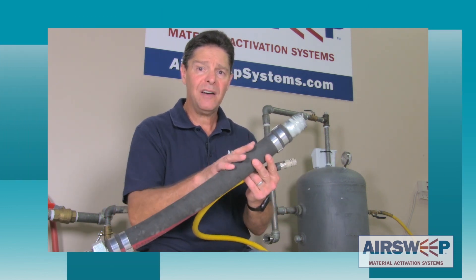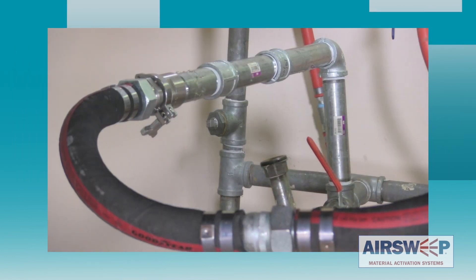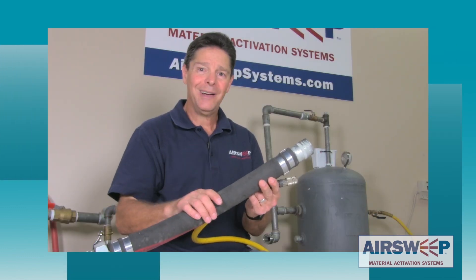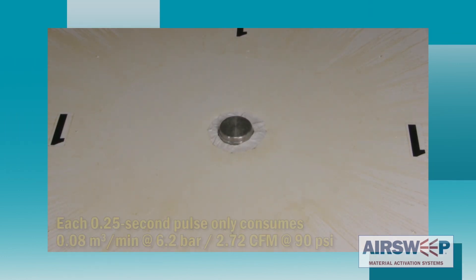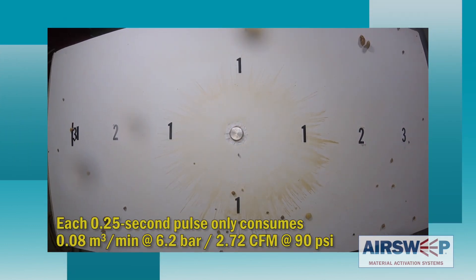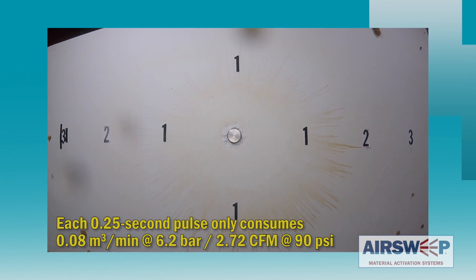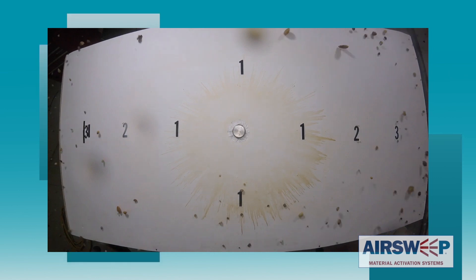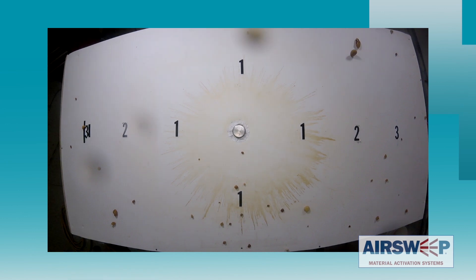Now we're going to hook up the inch-and-a-half line to the air receiver with big header pipe in between. That's going to provide some volume to the Airsweep — let's look at the difference. Running at full volume, it takes only one pulse from the Airsweep to completely clear the pile of wet rocks from the table. Wow! With the addition of more pipe volume the difference in clearing power goes from three inches to more than three feet.